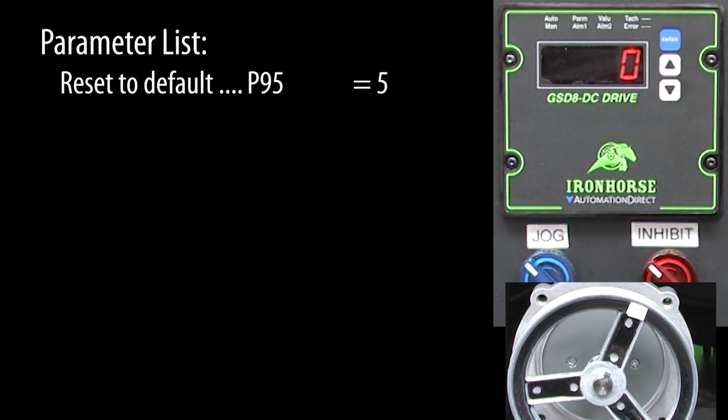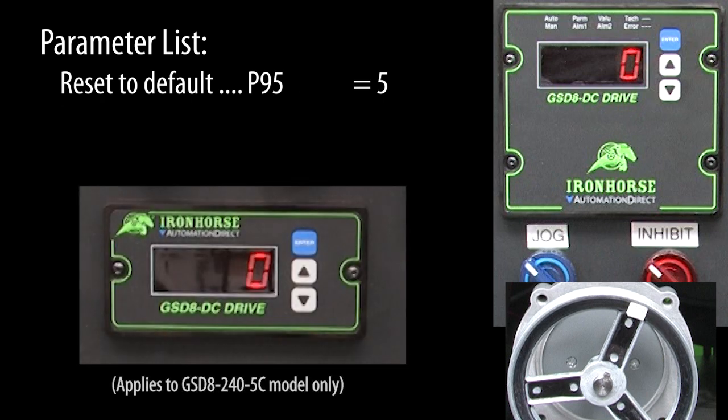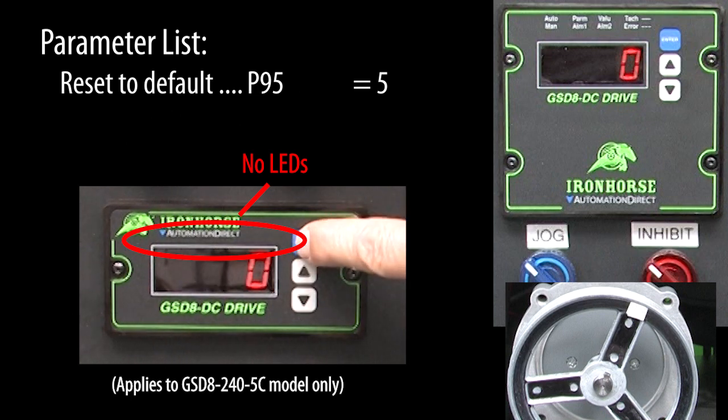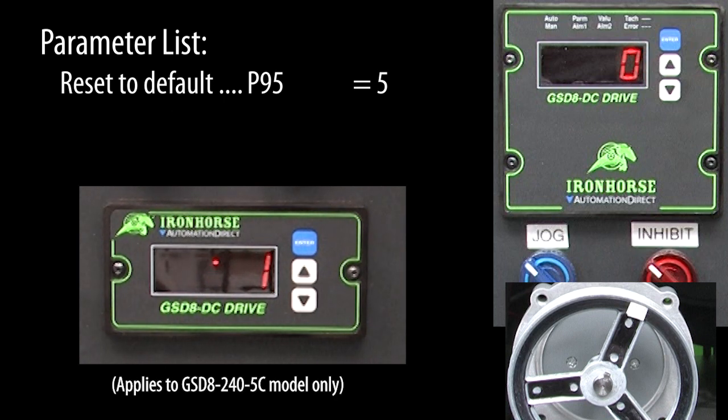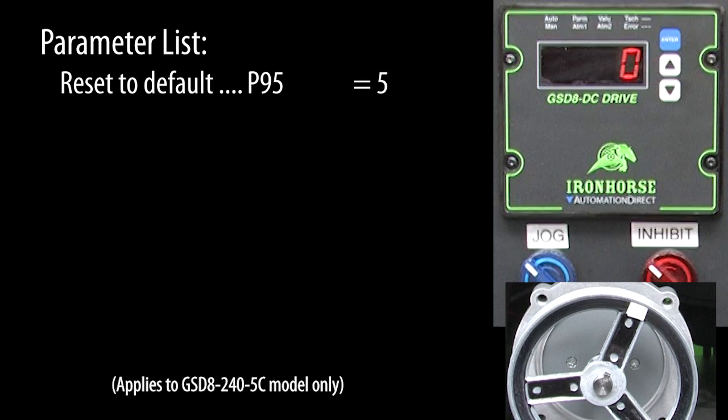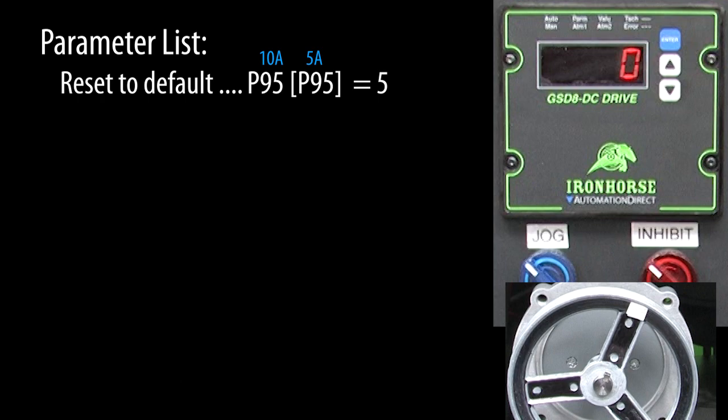By the way, this parameter entry method is exactly the same for the 5 amp drives but they don't have the LEDs to tell you what mode you are in. Instead, you will see a P for parameter entry and blinking dots for value entry. Also beware that the 5 amp model parameter numbers can be different. So don't assume that the parameter numbers I am using on this 10 amp model will be the same for the 5 amp drives. I'll put the 5 amp model parameter numbers in brackets to remind you.